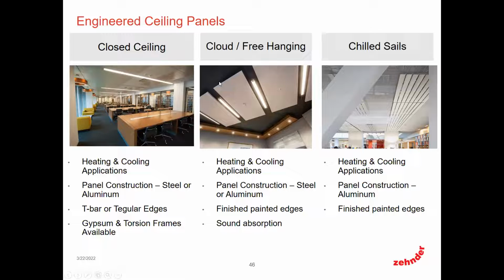Cloud or free hanging examples where you're open to structure. You can manufacture different panel sizes at this point, larger panel sizes because you're not tied to a hard lid, or you're not tied to a specific substructure at that point. And then the other option is the chilled sails, linear extrusion panels with copper tubes on the back side. These tend to give off more convective factors than they do radiant. So you typically see a little higher performance out of these.